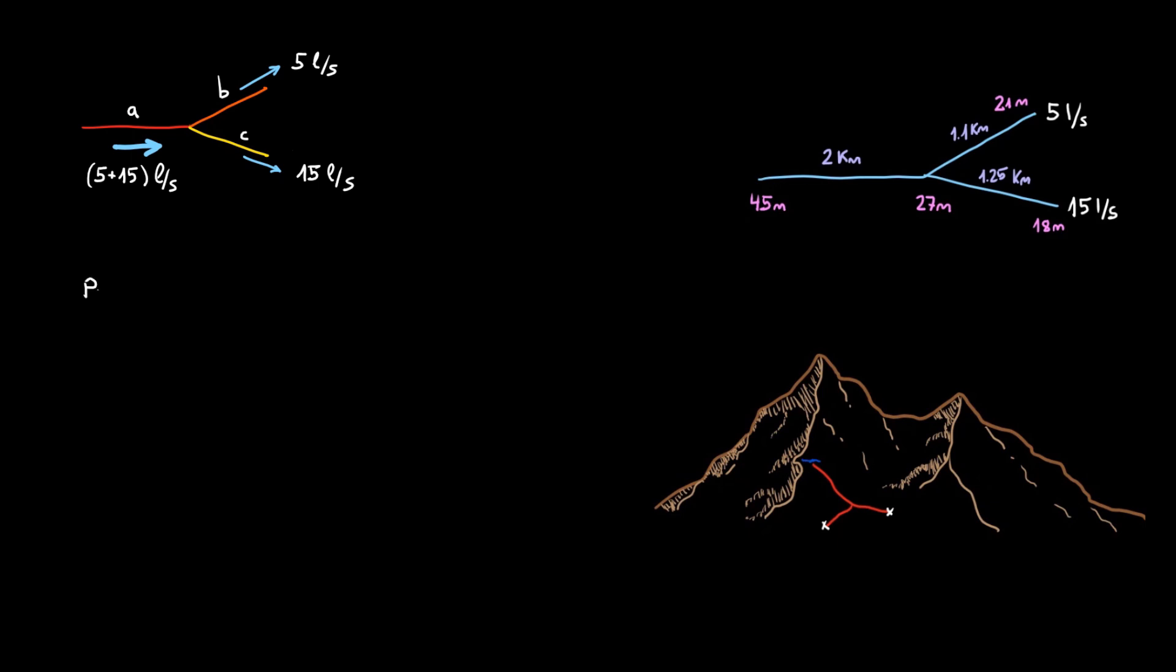So let's crunch the numbers for this particular system. We start sizing the upstream pipes. Step 1 is to find the maximum head loss for the stretch of pipe. Elevation difference, minus 10 meters of safety margin, over 2 kilometers. We need values lesser than 4 meters per kilometer.